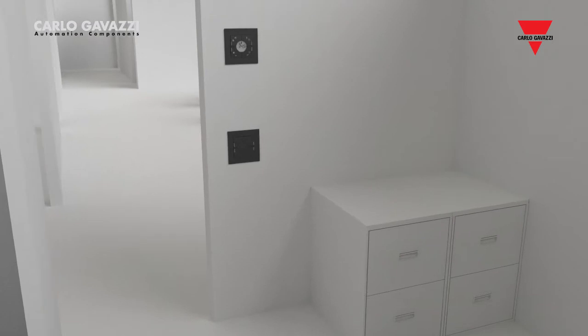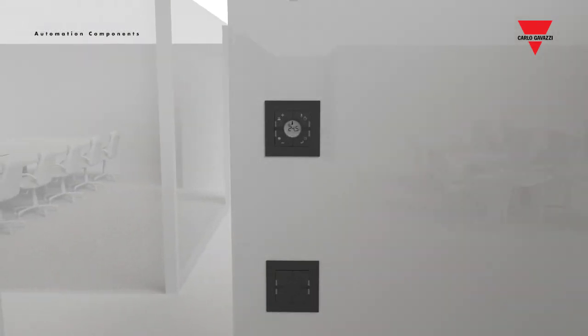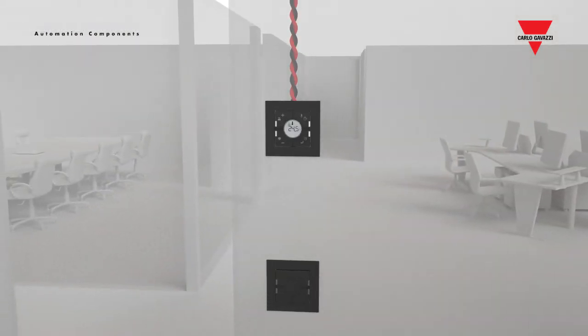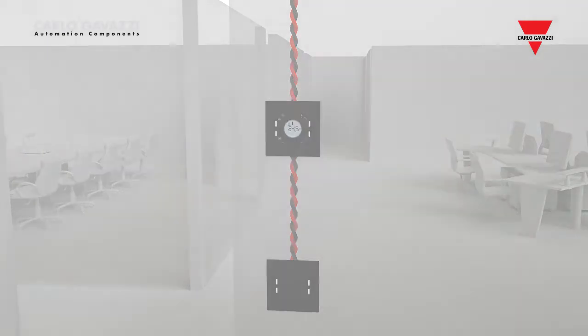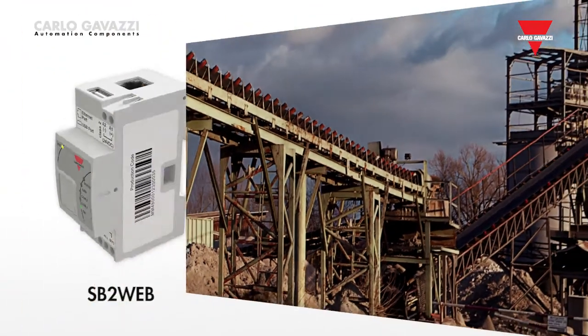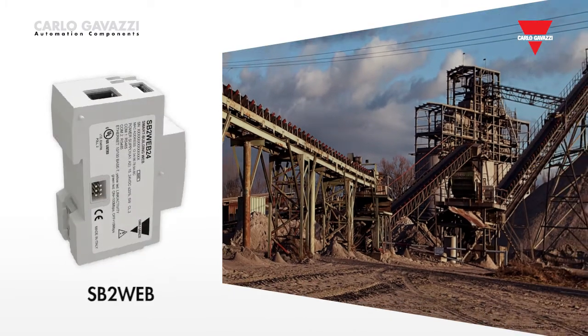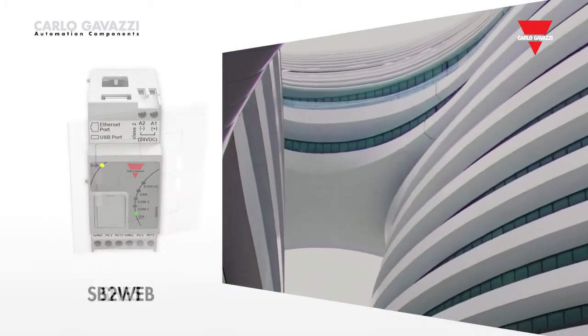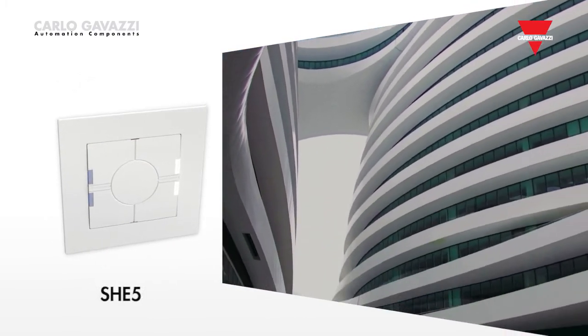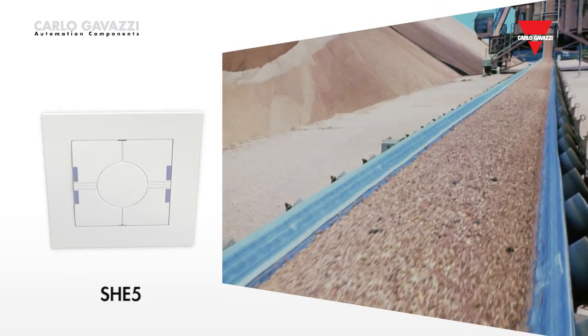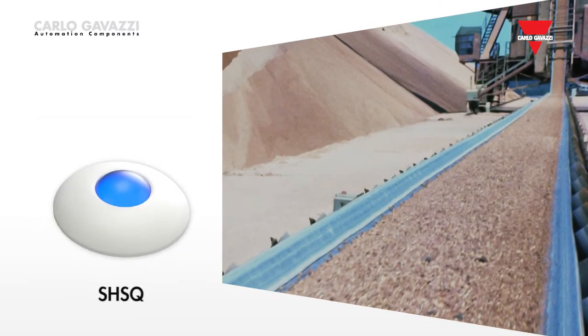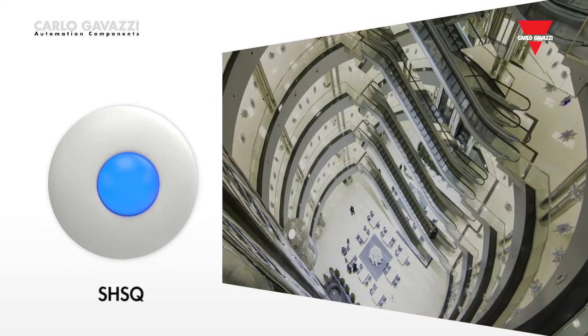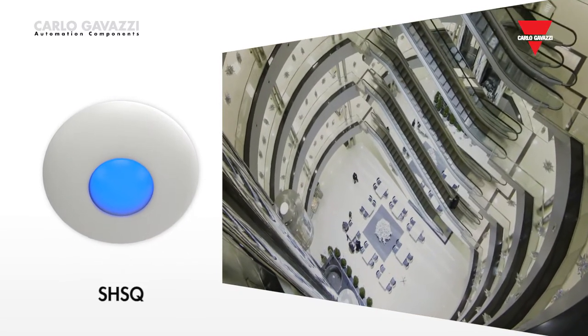So the installation is very easy, simply a question of multi-dropping the two-wire cable from one input-output point to the next. The savings are achieved at field level by using the flexible and cost-effective Dupline two-wire bus. With more than 150,000 installations in harsh industrial environments during the last 25 years, the robustness and reliability of the Dupline technology has already been proven.